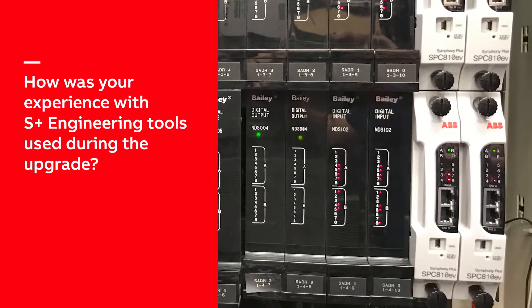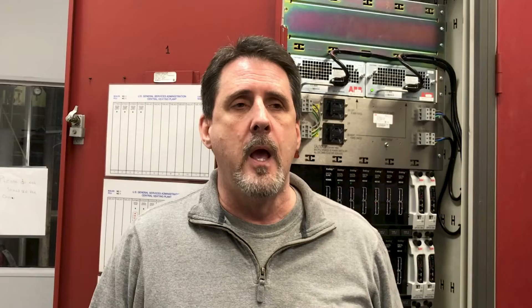The job that ABB did on this conversion tool is outstanding. This was probably one of the things that saved us the greatest amount of time on the project, because the conversion of both the logic and the translation of the peer-to-peer IO was seamless. We went through and did a full checkout of each of the IO points, loop-to-loop and module-to-module communication points, but found absolutely no issues at all.